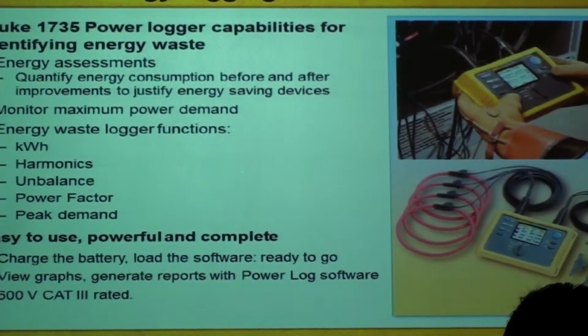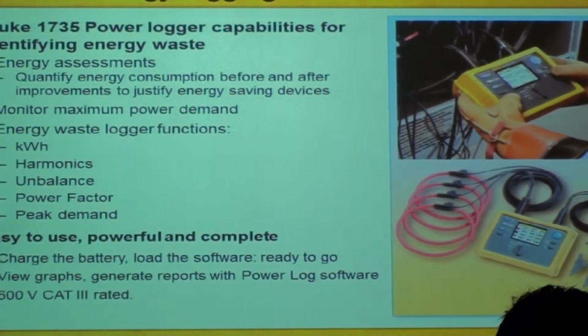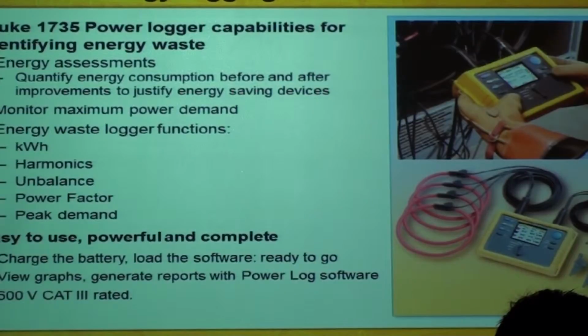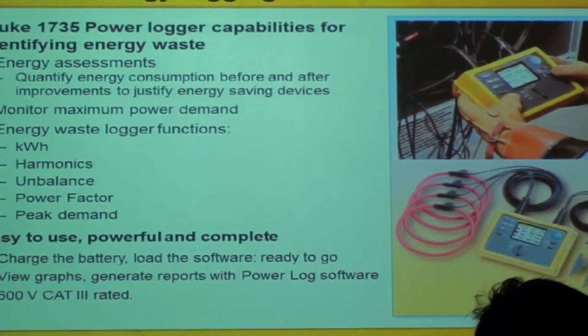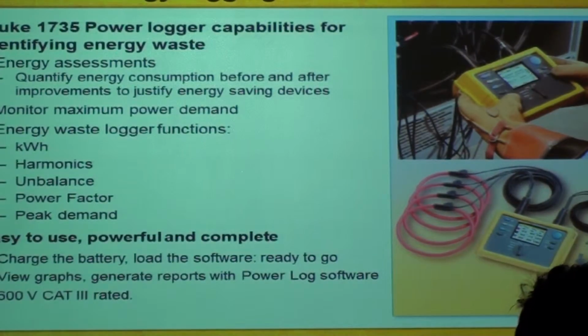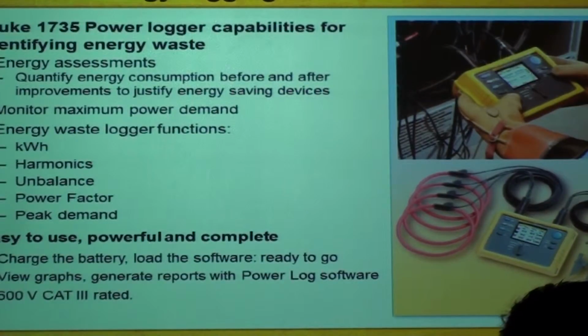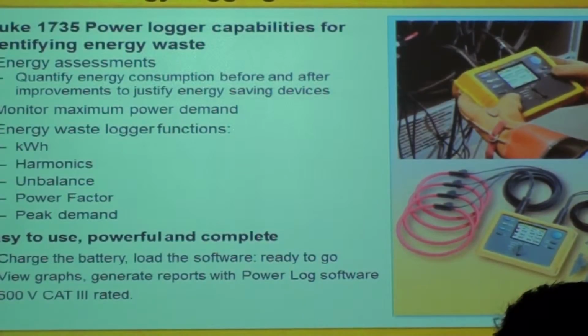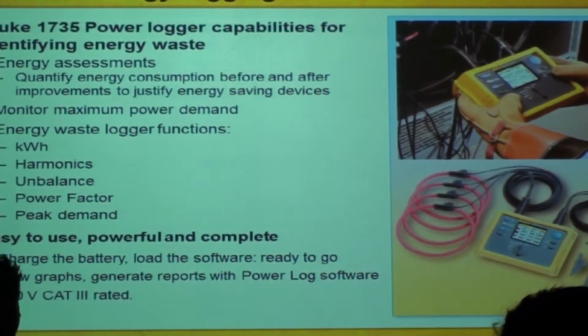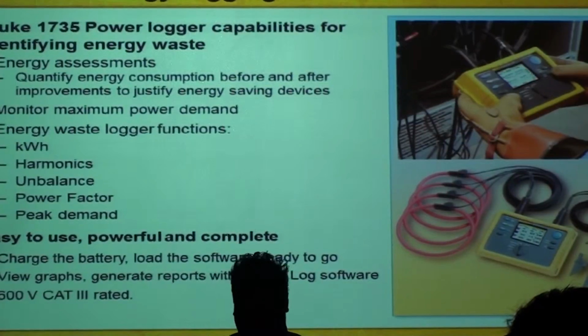So the point is, if you are working on a category 2 area, you have to use either a category 2 instrument or higher, never one that's below. Because if you use a category 1 tool on a category 2 area, that category 1 meter is not going to protect you if you have a fault in that category 2 area. So who decides these categories? The IEC. The IEC says if you're working in such an environment, the tool that you use must be certified to this category. But the problem is, the IEC does not go to every company, like Fluke, like Megger, like Greenlee, like whatever company you have, and check if Fluke is making Cat 4 meters. Are you making Cat 4? No. They just set the standards.